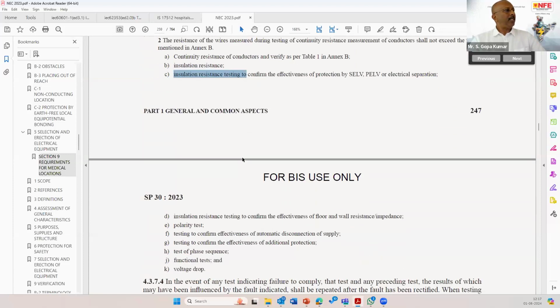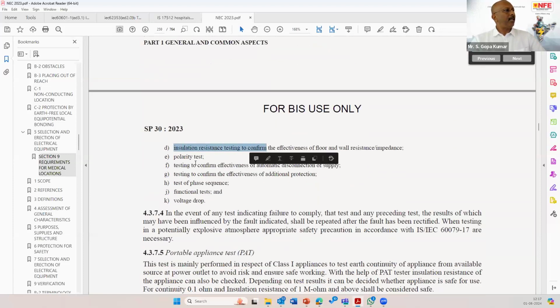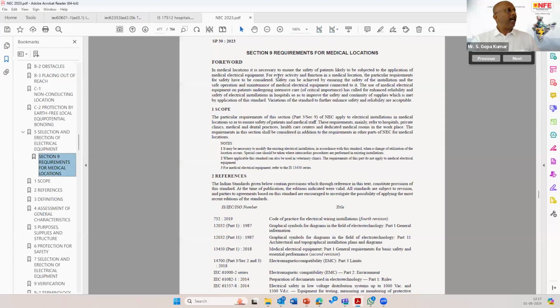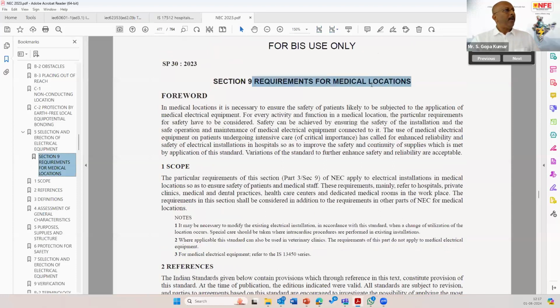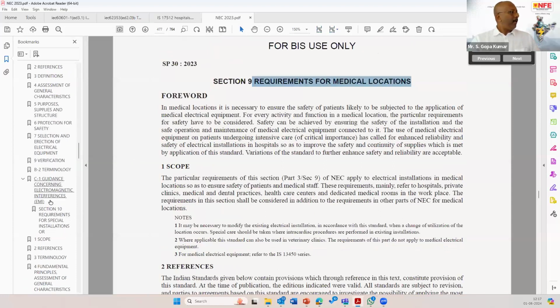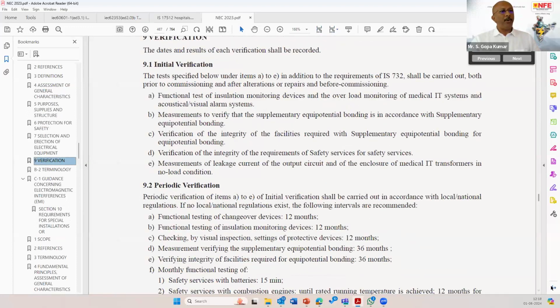Second, insulation resistance of PELV and SELV, and the effectiveness of floor and wall resistance. That means people standing on the floor do not get a shock. Then effectiveness of automatic disconnection of supply, and voltage drop. There are different tests included in the standard for a normal electrical installation. Now, for medical locations, you should go to part 3, section 9 of the NEC, requirements of medical location. Here you go to the clause on verification, the additional verification. Please note that these verifications are not for the equipment.